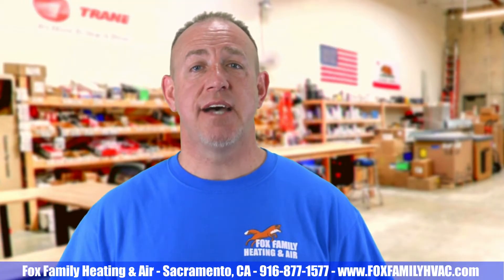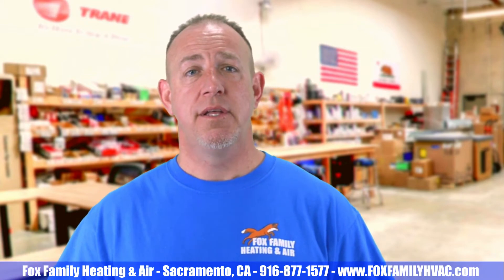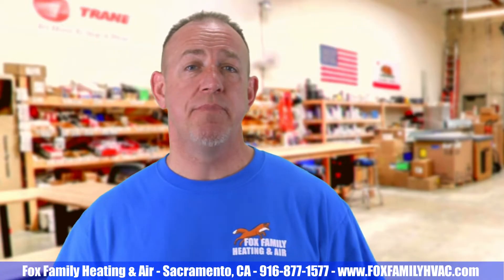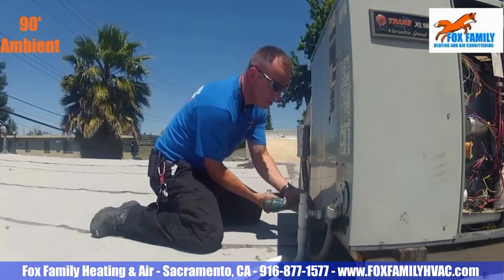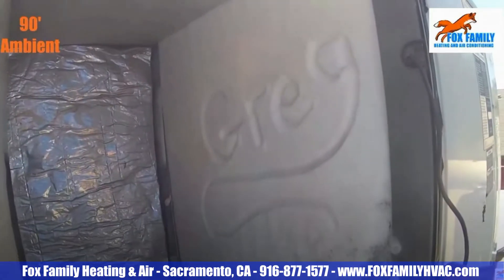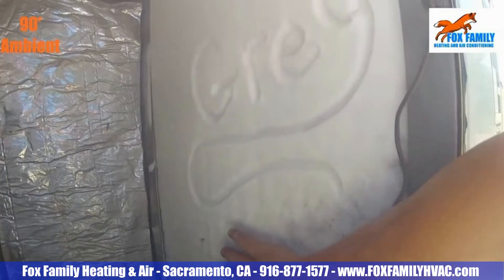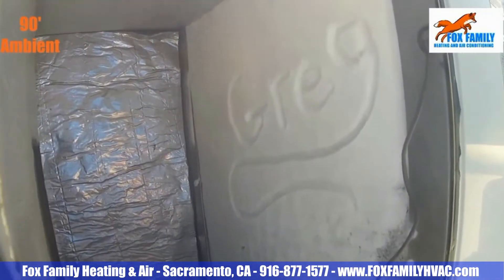Back to the gauges: the high side is normal to high and the suction side is looking a little lower than normal. I usually confirm this by adding a half a pound of refrigerant to see if the pressures go up. If you see that the high side rises but the low side doesn't respond, you're heading in the right direction as far as locating the problem. When the customer said the air cools fine at first, then it isn't cool and even stops flowing altogether, I just see all the little fins on the evaporator coil frosting up ever so slowly until it turns into a big ball of ice. Then air can't get through at all.